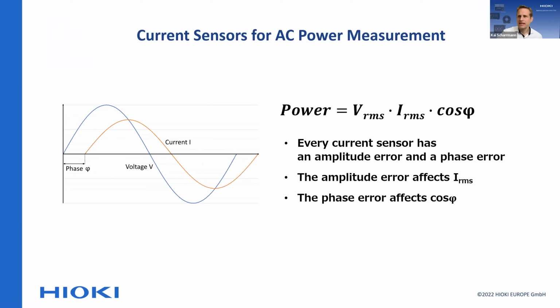Now it gets a bit more mathematical, but it won't get too mathematical. There are things you need to look at when making measurements with higher frequencies and higher currents, whether with a current sensor or a shunt system, since a shunt has the same effects inside. You have to look at the same information, characteristics, and specifications. One very important thing is the amplitude error, sometimes also called gain error, but I use the term amplitude error here.